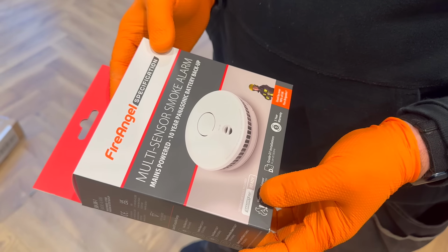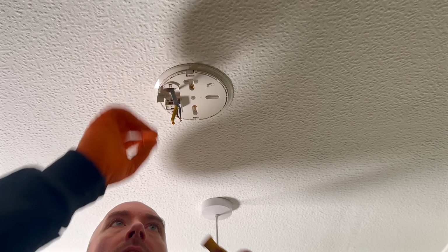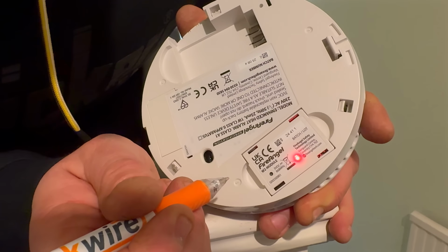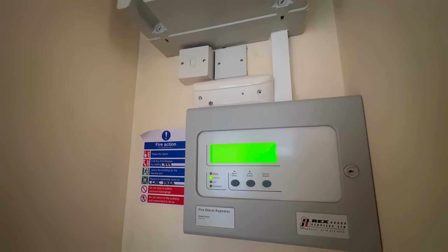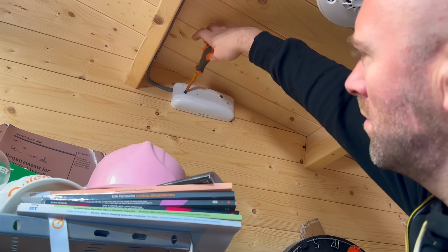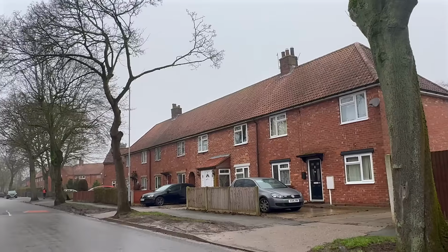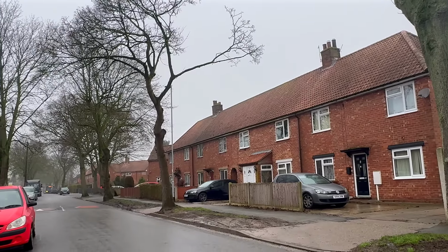And the FireAngel detectors, which can be interlinked together via a hardwire, an RF link, or a combination of the two, making them a hybrid system, more on that in the next video, can communicate with the central control panel via the FireAngel relay. The no volt relay will activate when the alarm sounds, which tells the fire panel a fire event has occurred and will activate the entire system. Whether the two systems need to interact is a separate design decision that may need to be explored prior to installation.